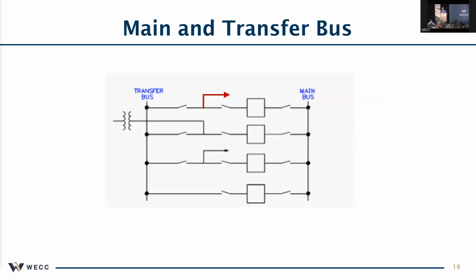Main and transfer bus, and what we're looking at now is that red line coming off the top. So with a main and transfer bus, you're going to be on the main bus 95% of the time, 98% of the time. So there's not a huge risk that you're going to be limited and have to set a rating based on going through the aux bus or the transfer bus, but it's possible. So for the auditors, this is their default. That's what they're going to consider. You should think of the rating as being from the main bus breaker out through the line and then of course to the other end. But like I say, you should also consider those other series components that could limit that facility, just to make sure that you're good.